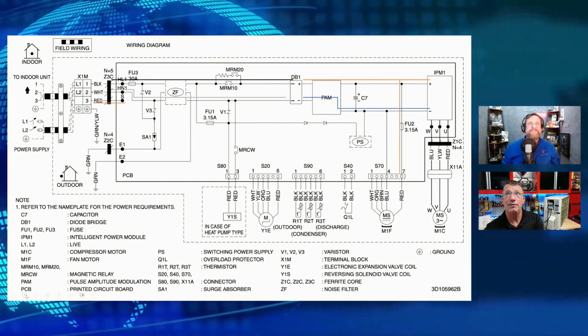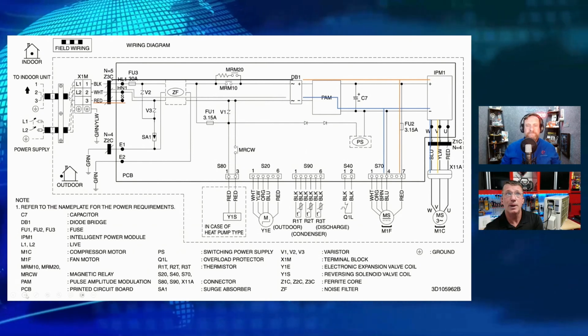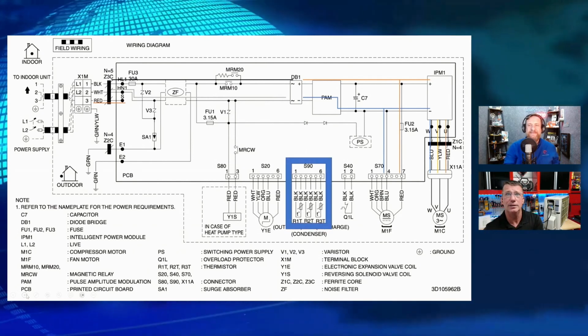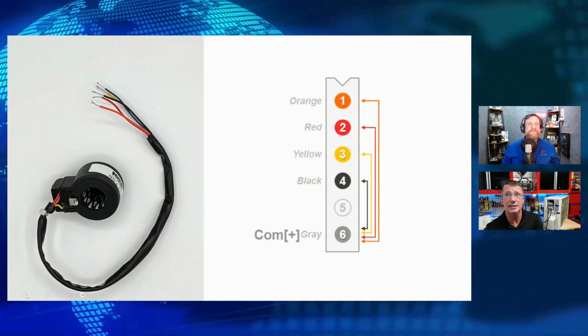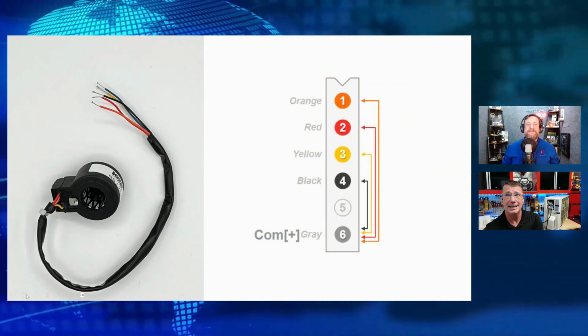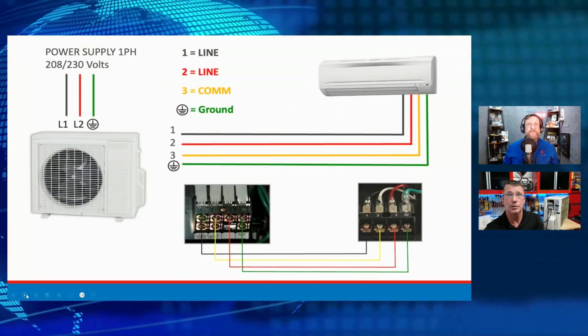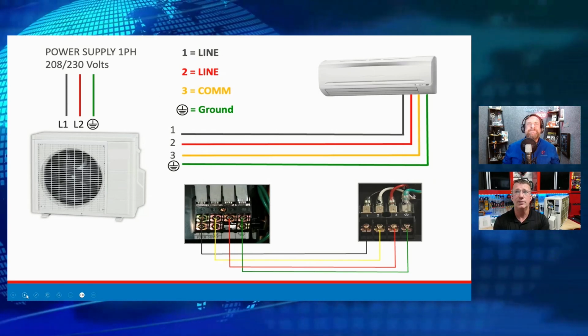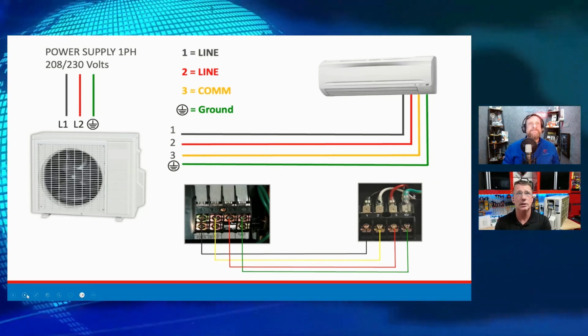All right, so that's how we feed DC to our inverter. And so that DC is going to be sent back around and utilized on that S terminal. I won't dive too deep into this one because this is how an inverter functions, but it's just showing that we are using AC and DC on all those. That DC voltage we're going to utilize as a constant 5-volt DC to run our pressure transducers, temperature thermistors, a variety of different things. All right, so let's take this 230-volt application, and I'll show you on this 120 what it looks like as well.